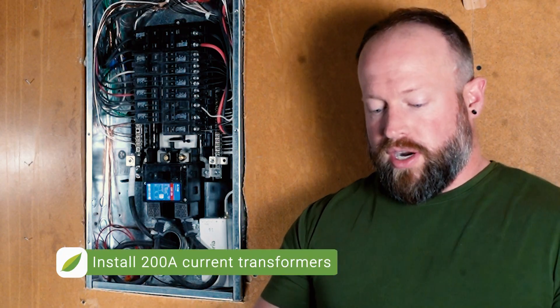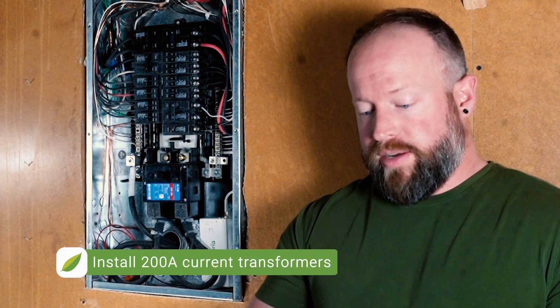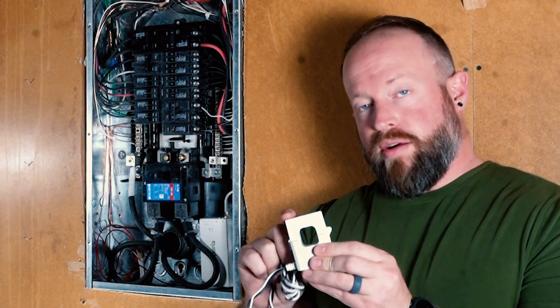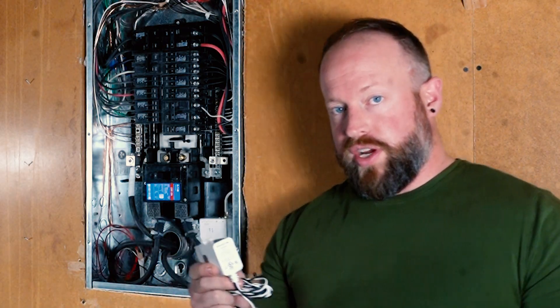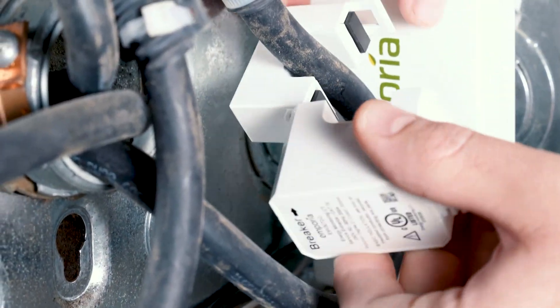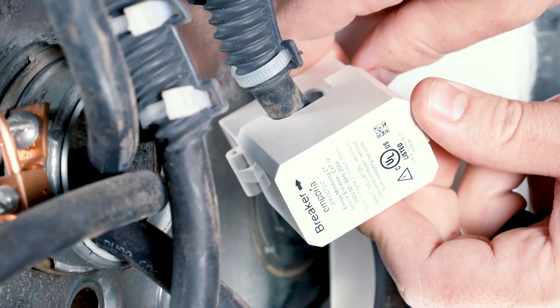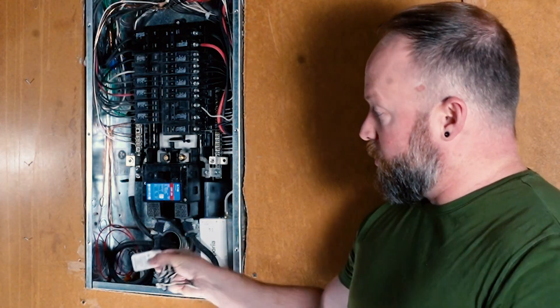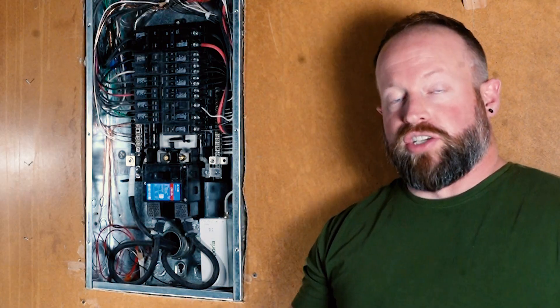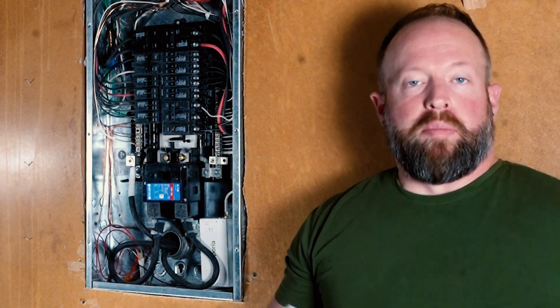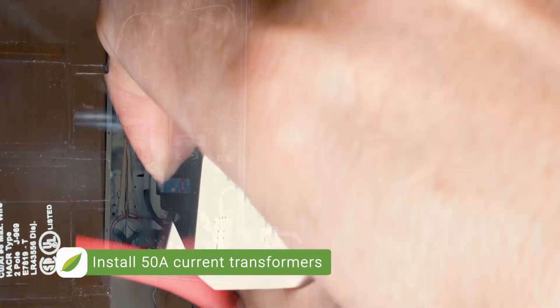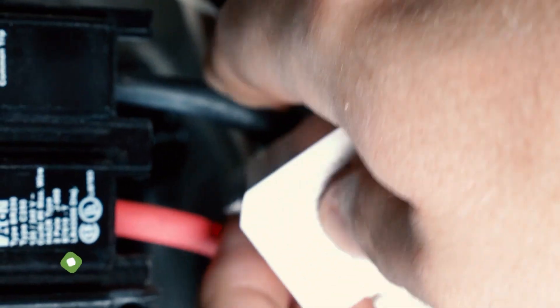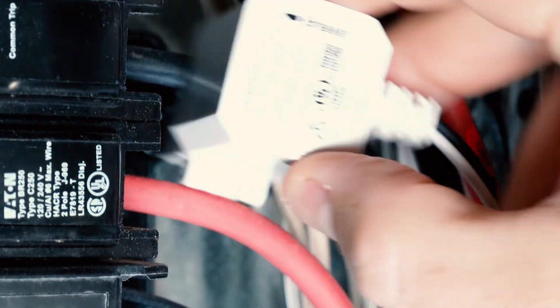These current transformers are clamshell type and they have a little clip where they open and they just clip around the wire that you want to measure. It's important to note that these current transformers have a label on the back of each one with an arrow pointing to breaker, and they need to be installed so that arrow is pointing at the breaker. Otherwise, the current that they are measuring will be registered as negative and will come up as negative in the app. The 50 amp current transformers also have an arrow pointing towards the breaker.